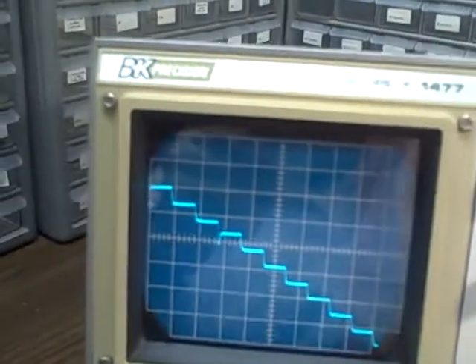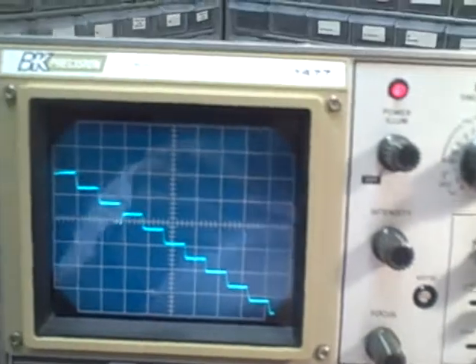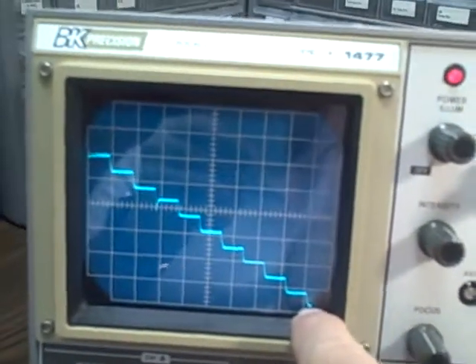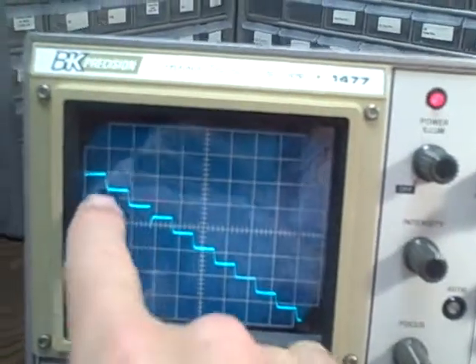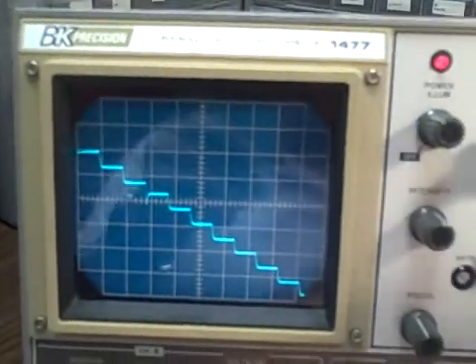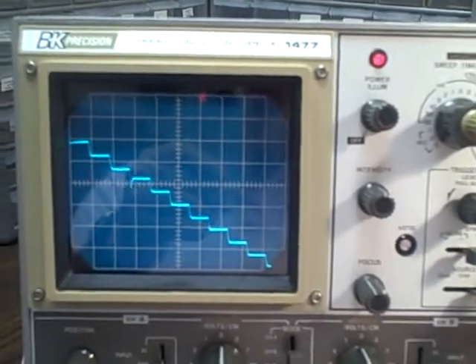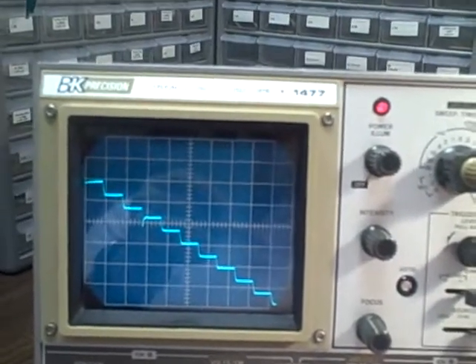One microsecond per division, and we are at the limit of our calibrator's capability. But once again, we see that we are zero to the right, one and a half in the middle, and three at the end — so we're still linear. So we've once again proven that on 0.5 volts vertical, we are calibrated through the entire range of the scope.